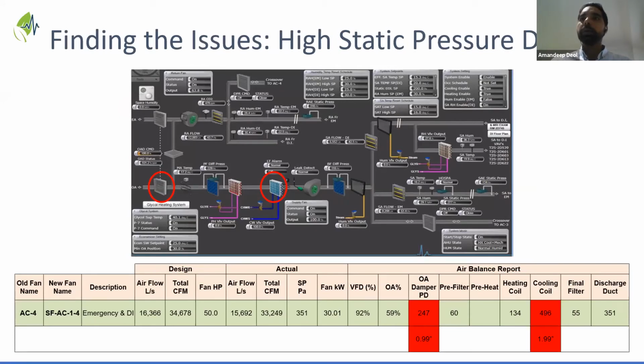This is another example here. If you look at the highlighted red section, which is the outside air damper pressure drop, when the system was measured with traditional air testing, it showed 0.99 inches, or almost 1 inch, of pressure drop across the outside air damper. And similarly, the cooling coil was around 2 inches of pressure drop. This is a very straightforward process in the air testing where you request your TAB contractor to come in and measure the pressure drop across the component, and it tells you a story on its own about why the system is not performing as expected.